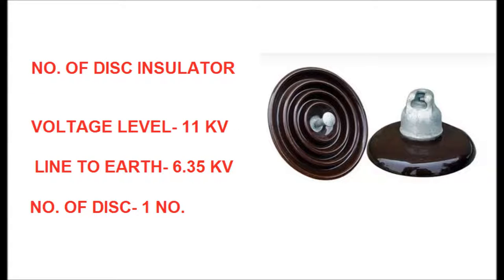For the 11 kV voltage level, the phase-to-phase voltage is 11 kV. The line-to-earth voltage is 11 divided by √3, which equals 6.35 kV. Therefore, it is sufficient to use one disc for a suspension type string, but for tension type, one more disc is added — that is, two discs are used for an 11 kV system.